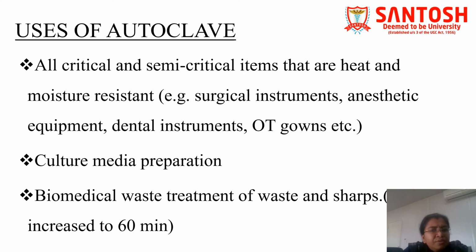It is used for all critical and semi-critical items which are heat and moisture resistant. Okay? For those items in which moisture will do no harm, they are moisture resistant, like surgical instruments, anesthetic equipment, dental instruments, OT gowns, etc. Then we can also use it for culture media preparation, and for biomedical waste treatment also autoclave is used. Only the time period is increased.